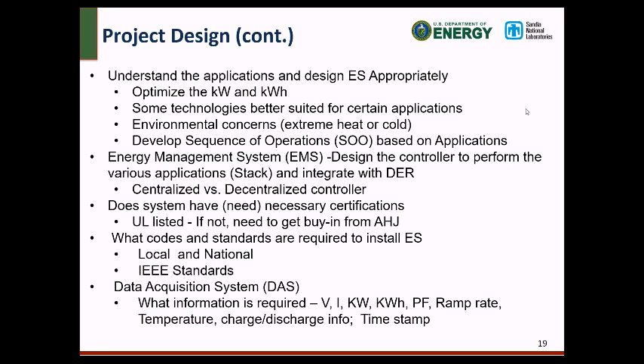Behind the meter, the system basically involves the inverter and the battery. Some of the batteries used to have a sticker, now they're getting UL listed, which is a change. So it's an evolving process, but the questioner is right, there are other testing agencies, but be careful of what your AHJ will allow.